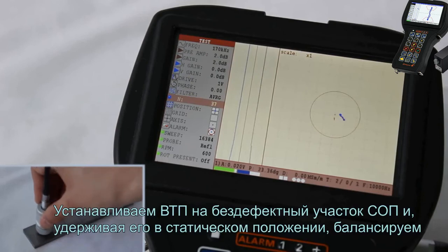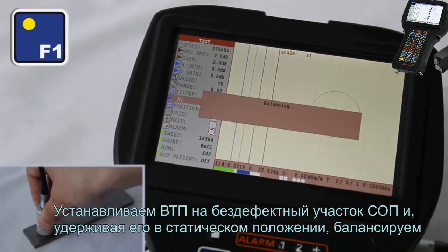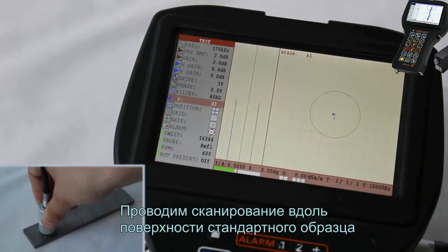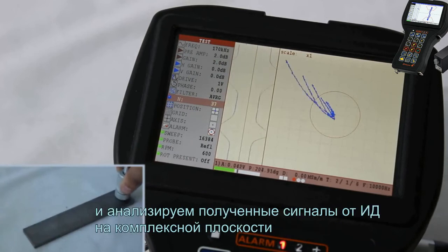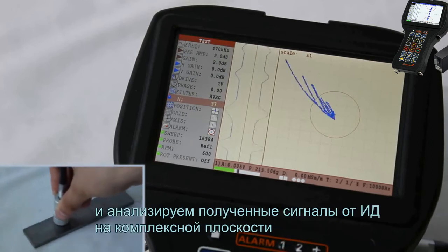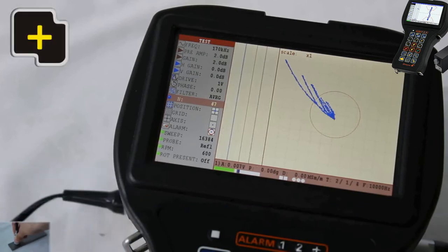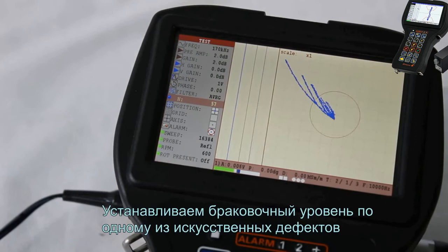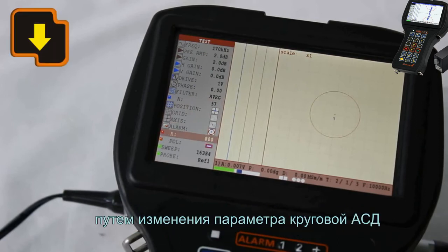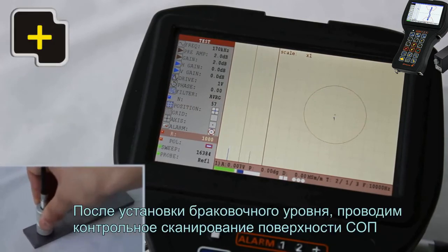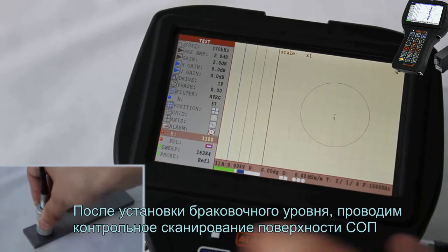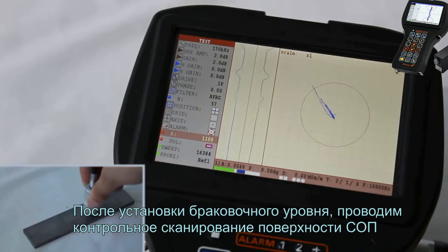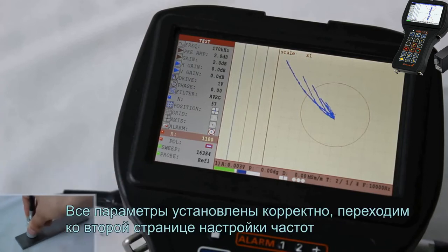Place the EC probe at a flaw-free area of the calibration block and by holding it in a static position, perform the balancing. Carry out the scanning along the surface of a calibration block and analyze the received signals from artificial defects in a complex plane. Set up the acceptance level by one of artificial defects by changing the parameter of circle alarm. After setting up the acceptance level, carry out the control scanning of a block surface. All parameters set up correctly.